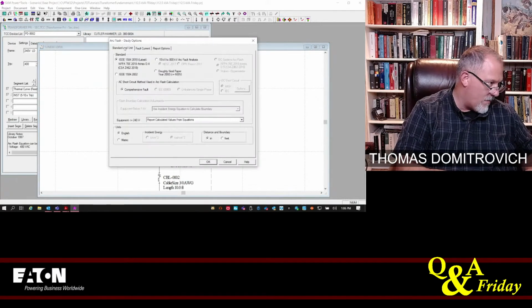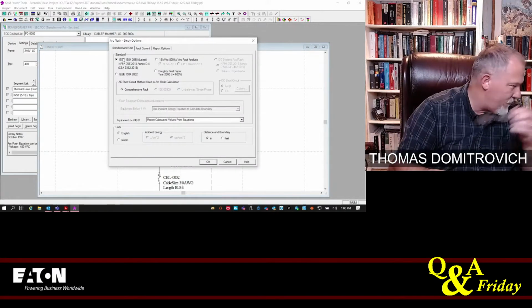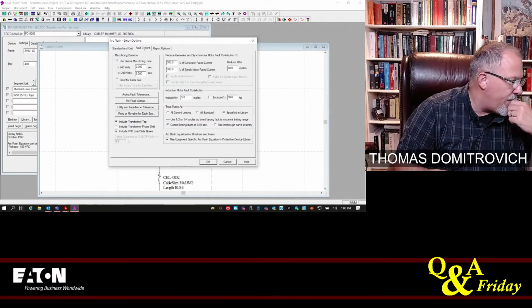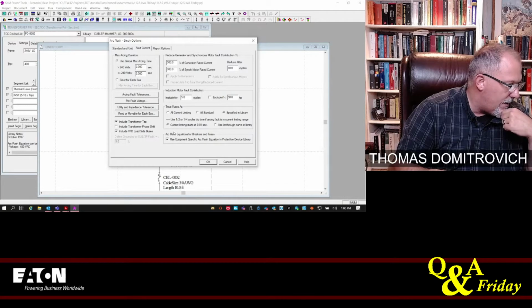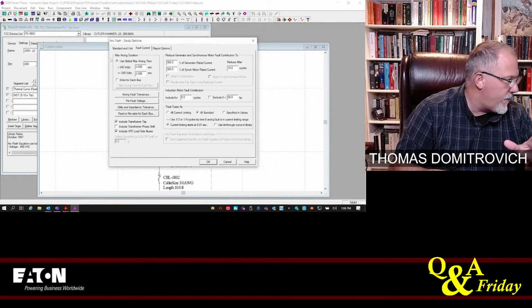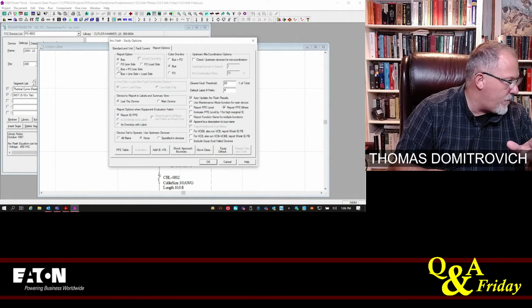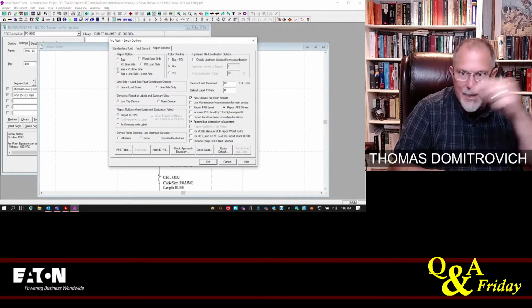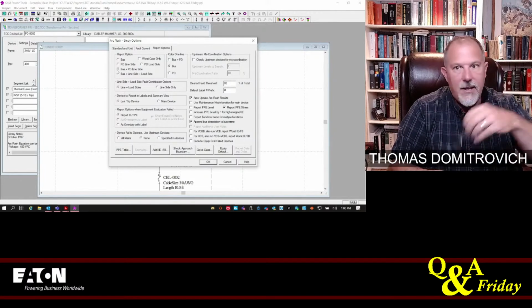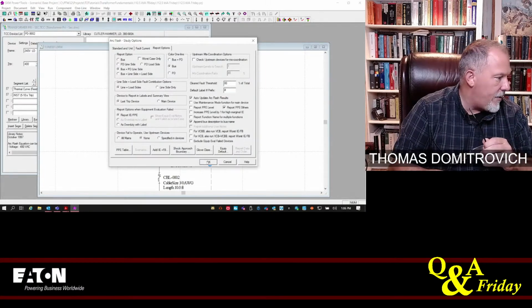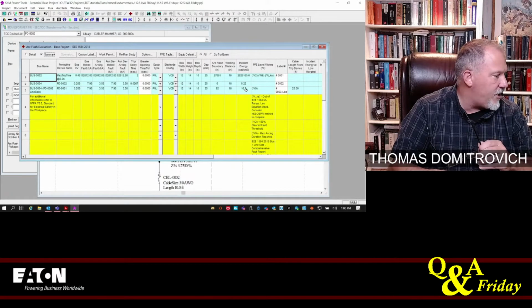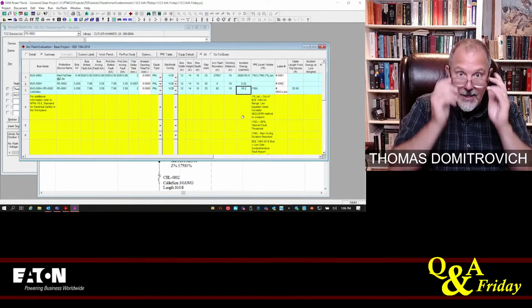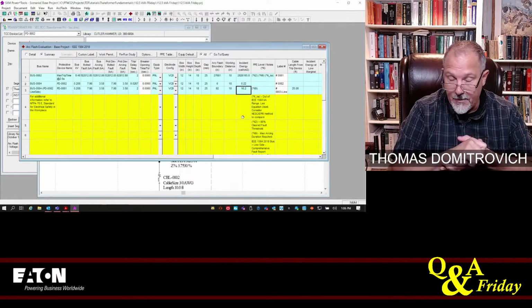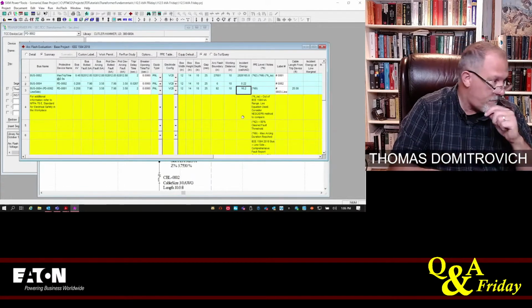All right, so I'm going to use the 2018. My fault current, see if there's anything I have to change on here. I don't. I am going to do all standard for the clearing times. I'm going to do bus plus the line side. I've got to consider line side propagation. I'm going to hit OK. Incident energy at that panel 4 is 16 calories. 16 calories.